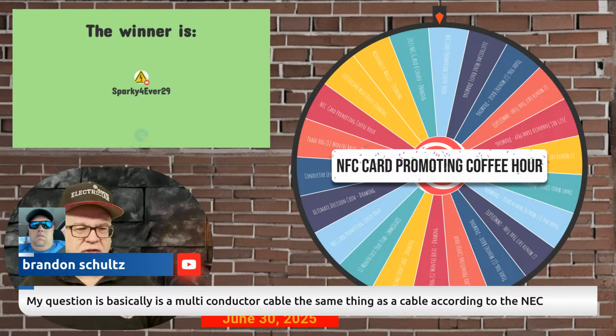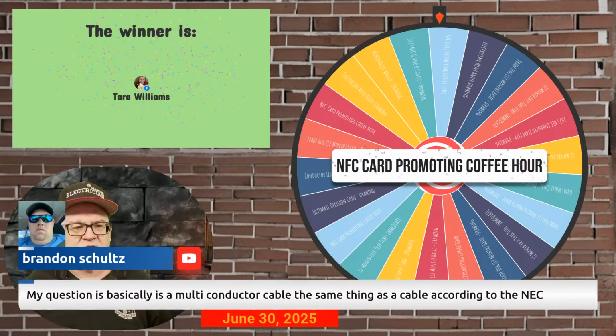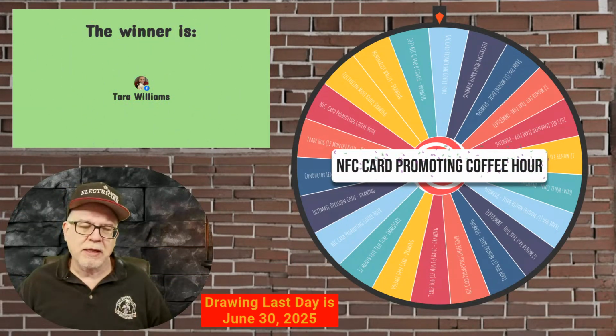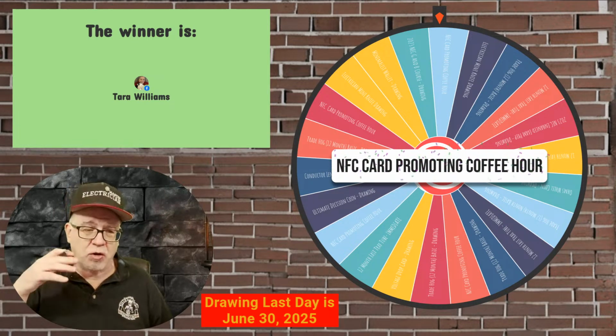Brandon, I'm not sure what you're saying. A multi-conductor cable is where you have two or more conductors on a cable together. Single conductor cable is based on its construction. It's called a cable because it has an inner core, copper, aluminum, whatnot. It has insulation, and it typically has another sheathing on top of it.